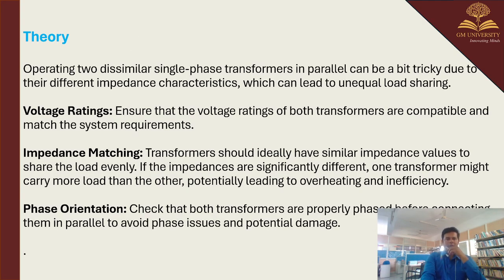So, theory. Connecting two dissimilar transformers in parallel is very tricky, because their different impedance characteristics can lead to unequal load sharing. The conditions required for parallel operation: first, the voltage rating. Ensure that the voltage ratings of both transformers are compatible and match the system requirement. Then we require impedance matching. The transformers should ideally have similar impedance values so that they share the load evenly. If the impedances are significantly different, one transformer can carry more load than the other, potentially leading to overheating and inefficiency of the transformers.